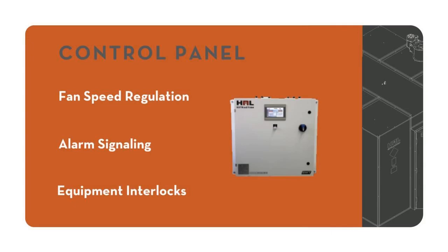So here are a few interesting items, at least for a HAL panel, that work with the panel components. The first one is fan speed regulation. The HAL unit specifically is designed to have modular variable airflow. So what it means is if the room is below 10% of that lower explosive limit threshold, then it's just going to run at a base air rate. If the sensor detects something above 10%, it's going to send a signal through the control panel and then out to the fans to speed up the fans.